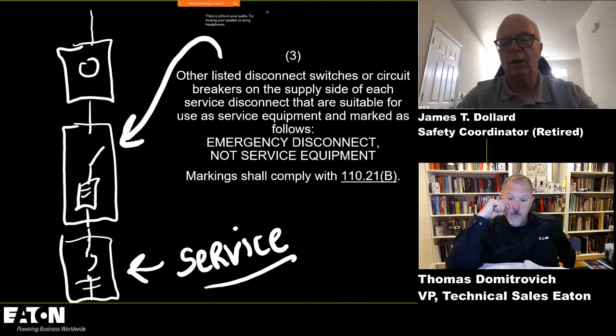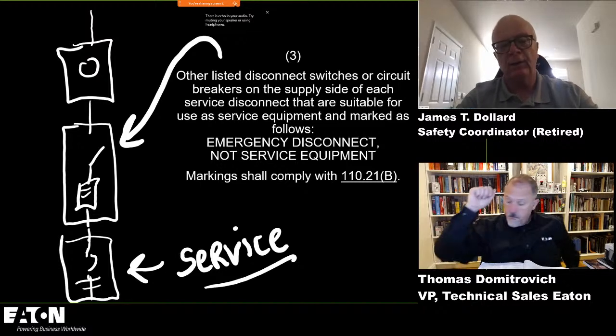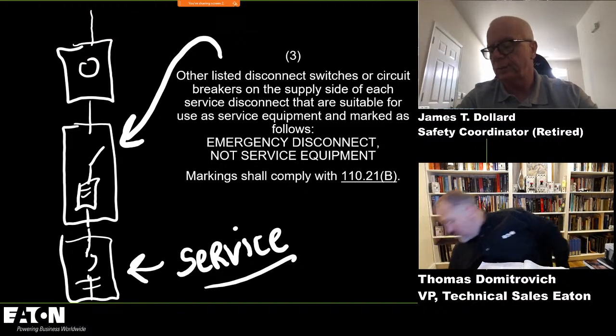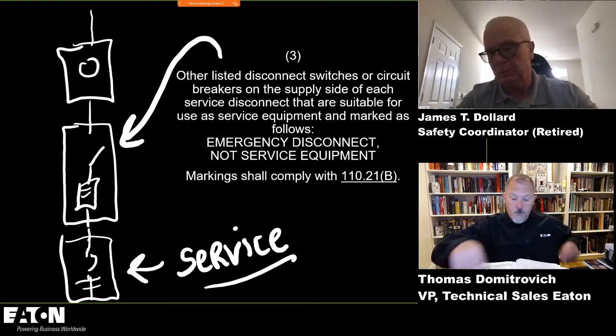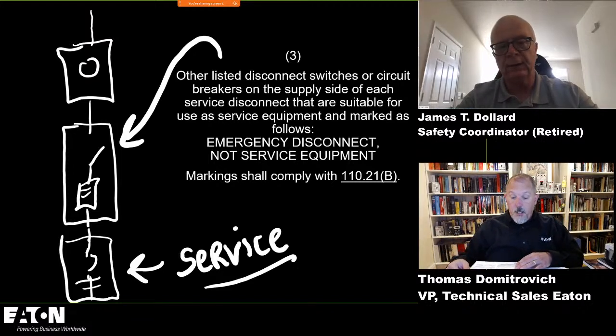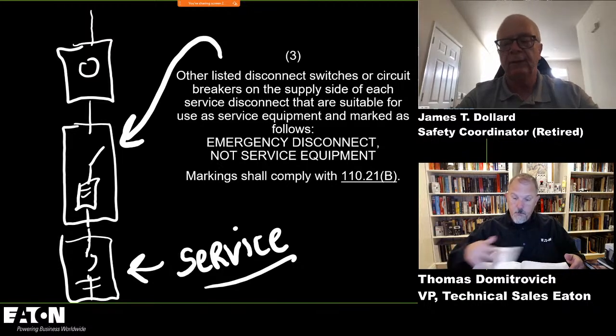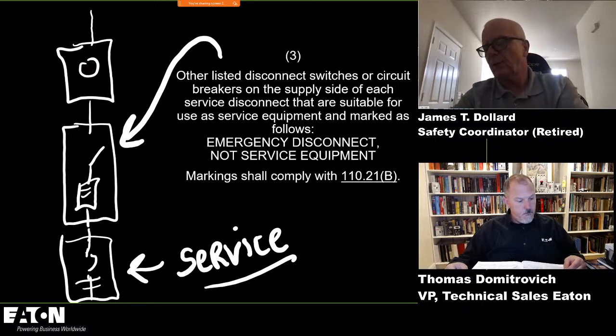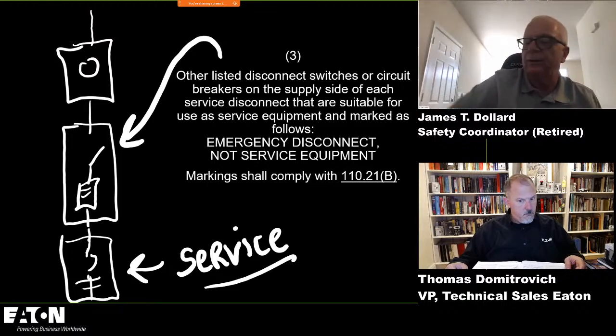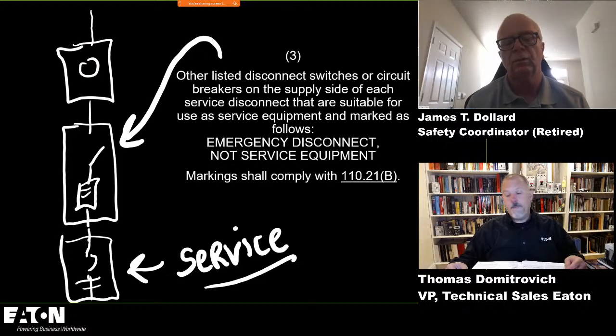But I don't think the utility would be very happy if you put a disconnect in front of their cash register. No, I don't think they would. But for the utilities that do require cold sequencing, the meter disconnect switch is inside the enclosure with the meter. Yeah, and they typically require that so that they can replace the meter in a de-energized state. Yep.